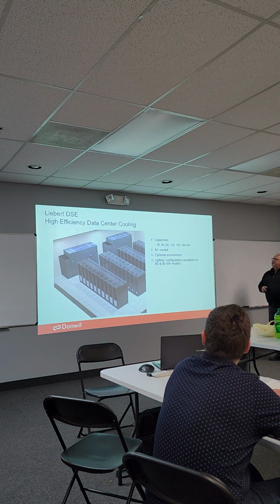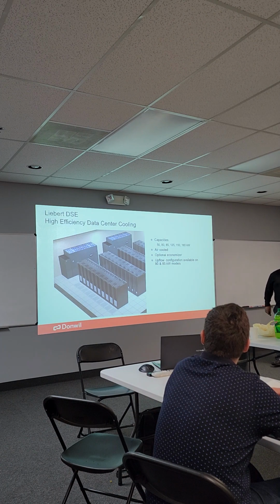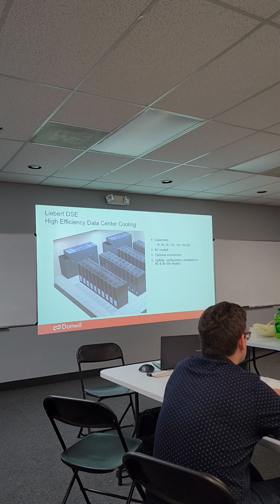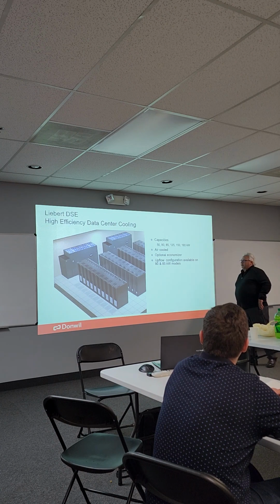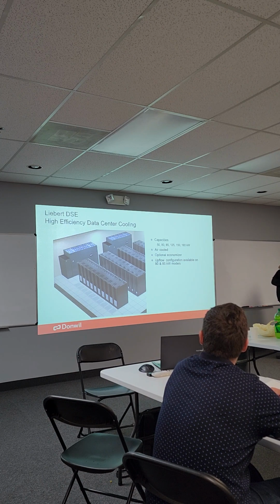So years ago, we repped a company called HiSave, which was a pump system that they put in the liquid lines, and it would lower the pressure of the discharge of a compressor, and we would save energy that way. Well, Liebert's engineers took that same idea another step and said, what if we could pump the refrigerant, shut the compressor off, and just pump refrigerant? And how much money would we save then? We'd save quite a bit if you didn't have to run a compressor, and all you had to do is run a pump. So that's basically what we do.